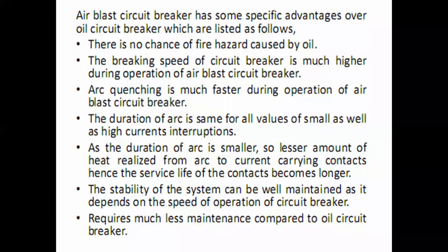The duration of the arc is the same for all values of small as well as high current interruptions. As the duration of the arc is smaller, a lesser amount of heat is released from the arc to the current carrying contact, hence the service life of the contacts becomes longer.